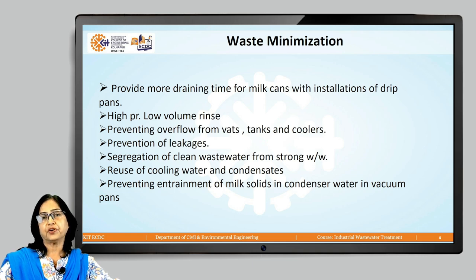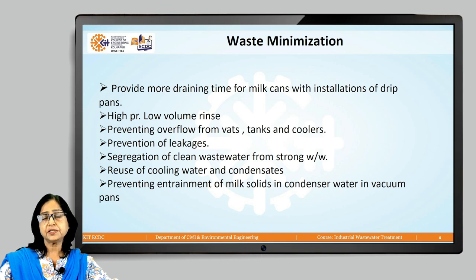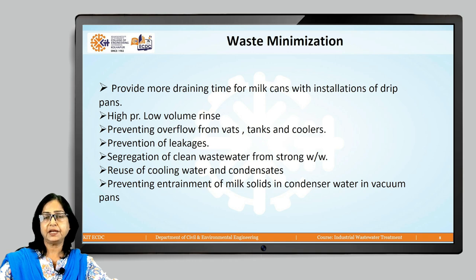Segregation of clean wastewater from strong wastewater is important. For example, most cooling water used is indirect cooling and is free from contaminants; if segregated, it can be readily reused and recycled. Additionally, all measures should be taken to prevent entrainment of milk solids in condenser water, especially during vacuum evaporation, ensuring the water is free from contaminants and enhancing its potential for reuse and recycling.